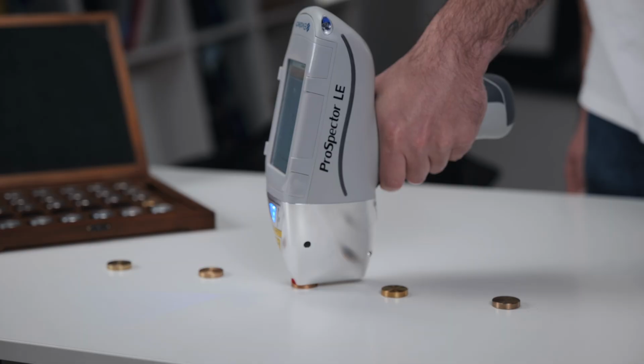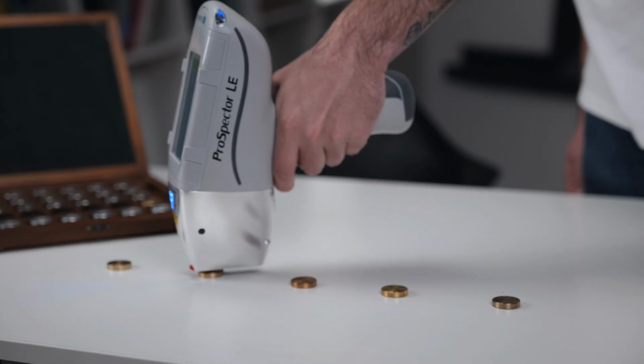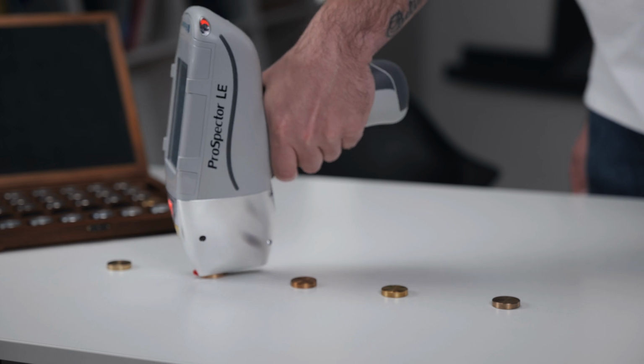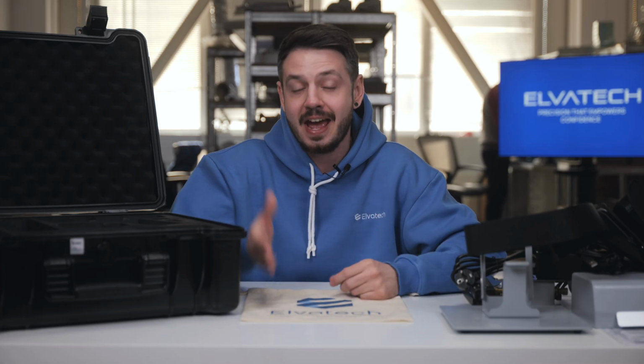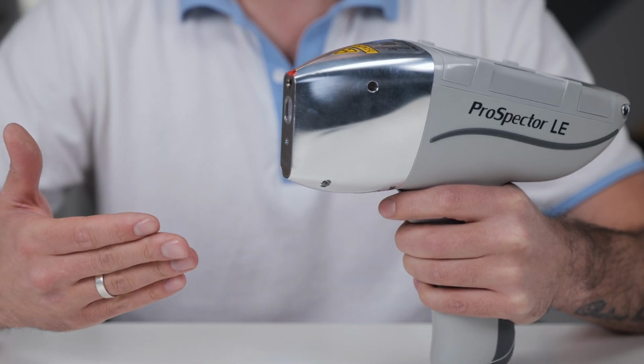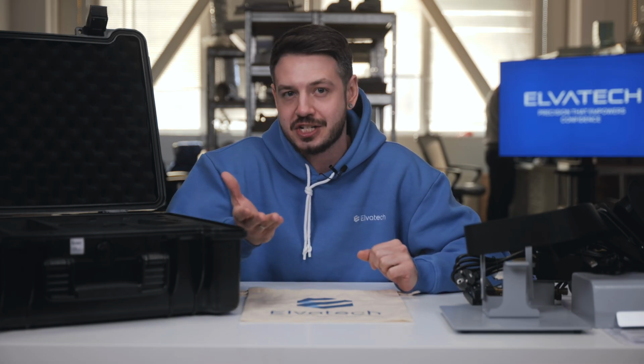As we said before, the ProSpector 2 is a reliable analyzer that was designed for stable and efficient operation. It features ambient temperature and pressure correction for consistent performance and offers over 8 hours of battery life for extensive field work. This analyzer ensures safety and convenience in use, with features like enhanced detector protection, easy replacement of the protective film without any kind of different tools, and an integrated barcode scanner for quick sample identification.